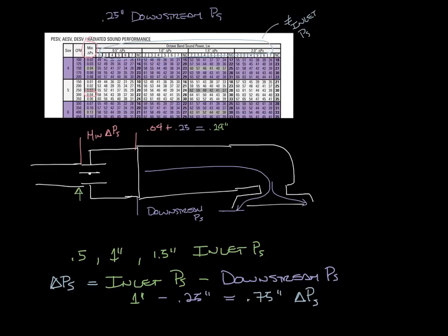So like the minimum delta P, the delta P shown in the table across the top of the sound data is the pressure loss across the box from the inlet to the discharge. So if I said that the minimum delta P is 0.04 inches, why would I have, say, a 1/2 inch delta P? Basically, the damper is closed down to maintain the 300 CFM through the box.